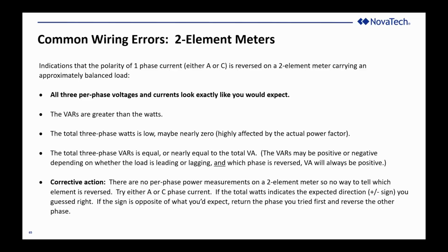It may be 0, but because the rate of change of the sine function near the 0 crossing is a lot faster than the cosine, which is at a peak near 0, your power factor affects the VARs very much in this range. So your three-phase watts is low. It may be 0, but because of the power factor, it may not be exactly 0. Total three-phase VARs is equal to or nearly equal to the VA, which is the same thing as saying the watts is nearly 0 because of the phase shift. Because of the sensitivity of the sine and the fact that the sine is not symmetrical about the vertical axis at the 0 point, you cannot depend on the sign of the VARs to indicate which of the two elements is reversed. That won't be a good indication.